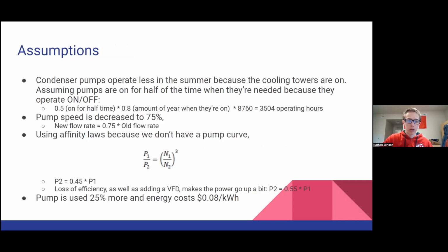Next slide, please. So here we wanted to put some assumptions in to just get some actual numbers. Looking at some of the notes that some of the people in the IC did at this assessment, they said that during the summer, some cooling towers are on, so the pumps aren't used as much. And so we assumed that because they operate on off, they're going to be on for half of the time they're needed, and then 0.8, so 80% of the year, because we're ignoring some of that summertime. So we get their current operating hours from that assumption. We assume that we're going to decrease the pump speed by 25%, which using the affinity laws lets us solve for our new power.